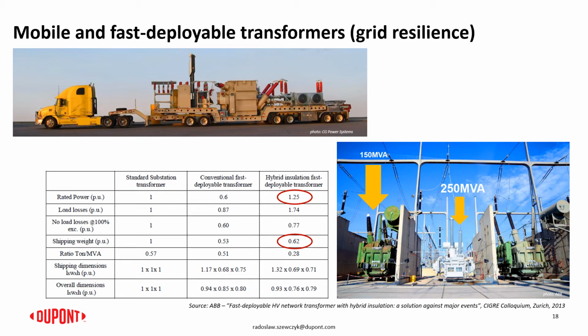We do not call them mobiles anymore. We rather call them fast deployable, because the size of the transformer or the voltage rating may not allow transportation of the units fully assembled, like the one on the picture in the bottom right, which is the case from Spain, where the 250 MVA transformer was designed and built with the Nomex-based insulation system for achieving great compactness for the transportation.